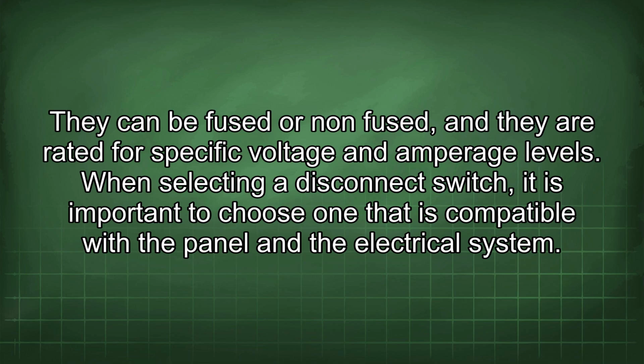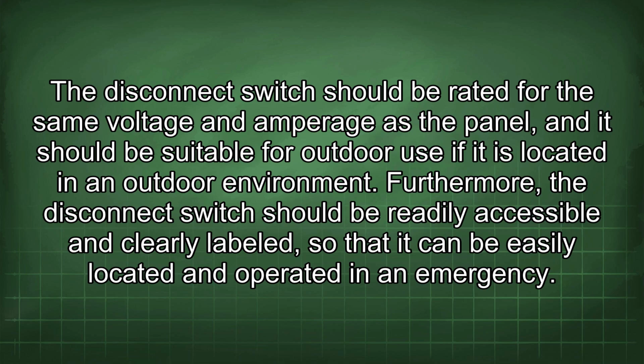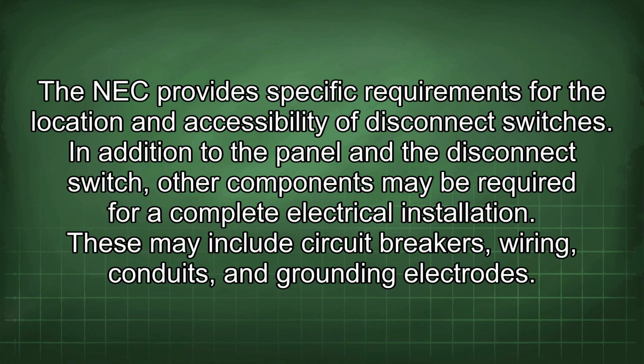When selecting a disconnect switch, it is important to choose one that is compatible with the panel and the electrical system. The disconnect switch should be rated for the same voltage and amperage as the panel, and it should be suitable for outdoor use if it is located in an outdoor environment. Furthermore, the disconnect switch should be readily accessible and clearly labeled, so that it can be easily located and operated in an emergency. The NEC provides specific requirements for the location and accessibility of disconnect switches. In addition to the panel and the disconnect switch, other components may be required for a complete electrical installation.